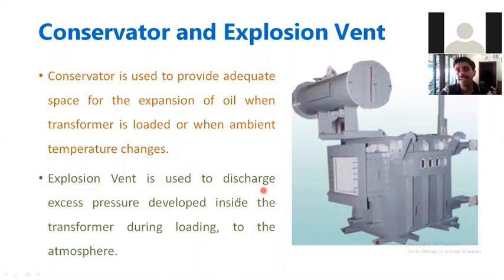Explosion vent is used to discharge excess pressure developed inside the transformer. So there will be a vent so that any excess pressure can be removed during loading conditions. That is the use of this. Next, the breather. You can observe the purpose of the breather is to remove moisture from the air entering the oil. If moisture enters the conservator, into the oil, it will reduce the dielectric strength of the oil. That means the insulation property will be reduced. So the breather has silica gel, which has the property of absorbing moisture. That is the purpose of the breather. Here you can see a ball shape. This is the conservator. Inside this is the oil level gauge. When the oil expands, it will go like this.